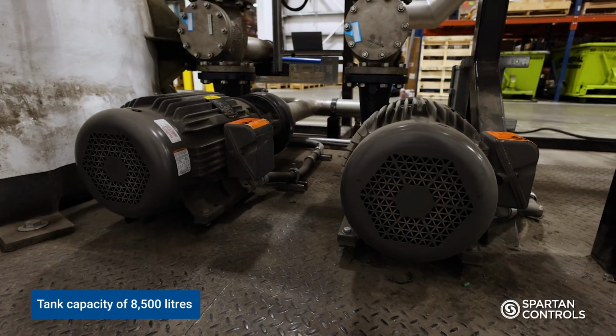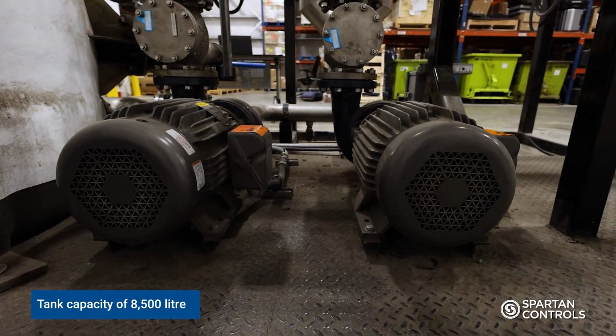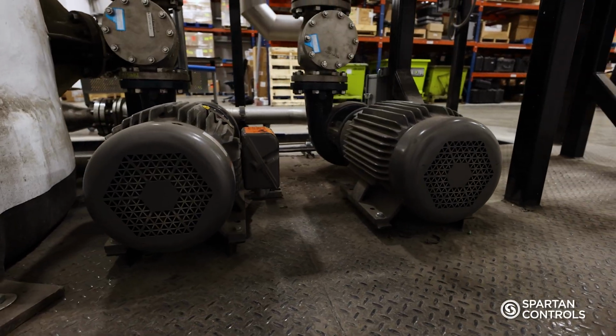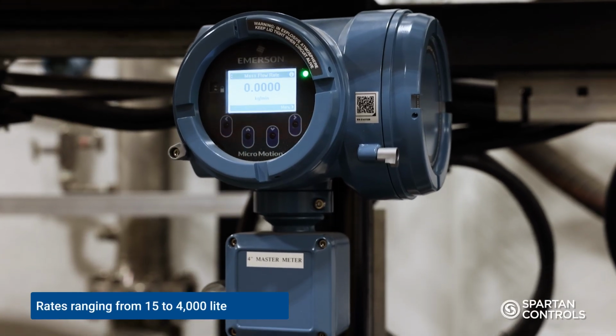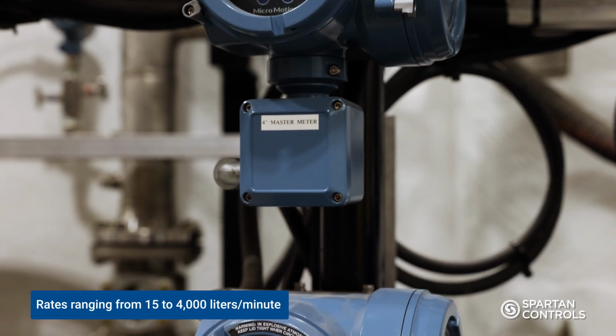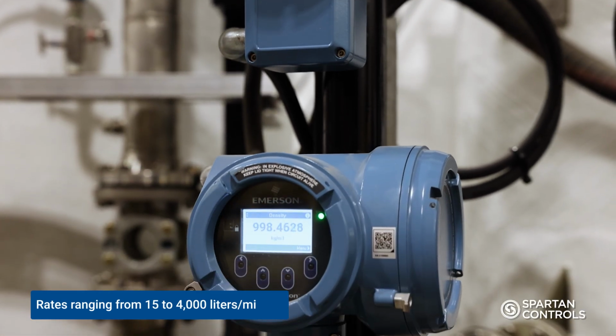With a tank capacity of 8,500 liters and 2 parallel centrifugal pumps, the stand is capable of cycling clean water through test meters at rates ranging from 15 all the way up to 4,000 liters per minute.